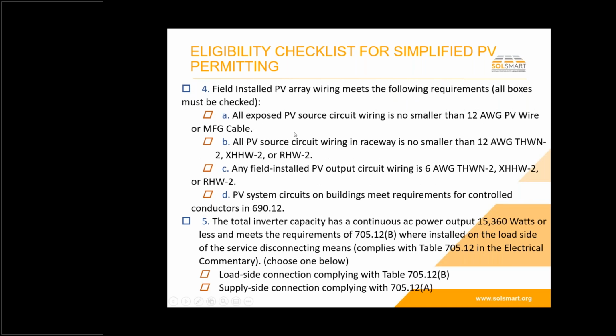Okay, continuing the electrical requirements for Simplified. The field installed array, basically the exposed wiring, so all the cabling that connects the modules together or connects the DC optimizers or DC converters together, is no smaller than 12 gauge PV wire or manufactured cable. Those are the 2 options that are pretty much out there on the market, so that's a pretty ubiquitous compliance requirement, and easy to comply with because the products are there and they're used universally.